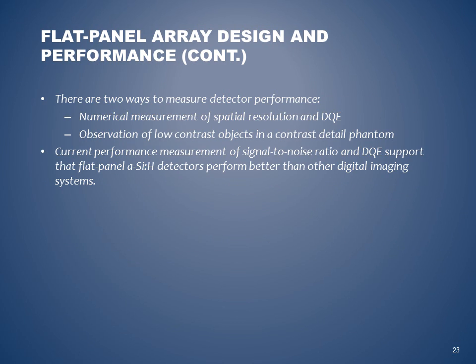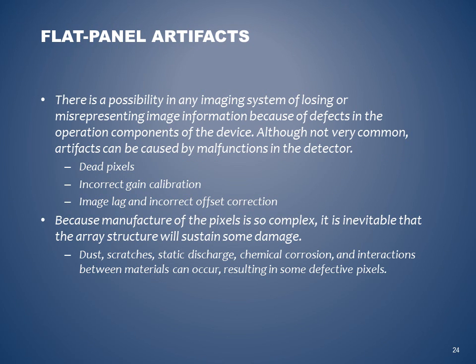There are two ways to measure detector performance: numerical measurement of spatial resolution and DQE, and observation of low contrast objects in a contrast detail phantom. Current performance measurements of signal-to-noise ratio and DQE support that flat panel a-Si:H detectors perform better than other digital imaging systems. There is a possibility of any imaging system losing or misrepresenting image information because of defects in the operation of components of the device. Although not very common, artifacts can be caused by malfunctions in the detector: dead pixels, incorrect gain calibration, image lag, and incorrect offset correction.